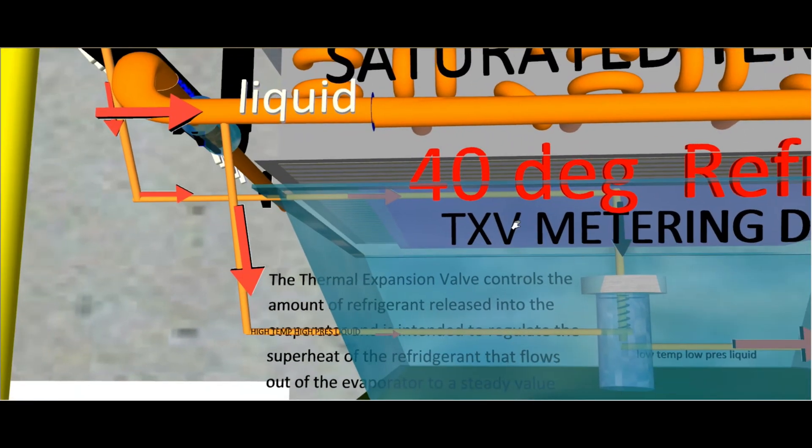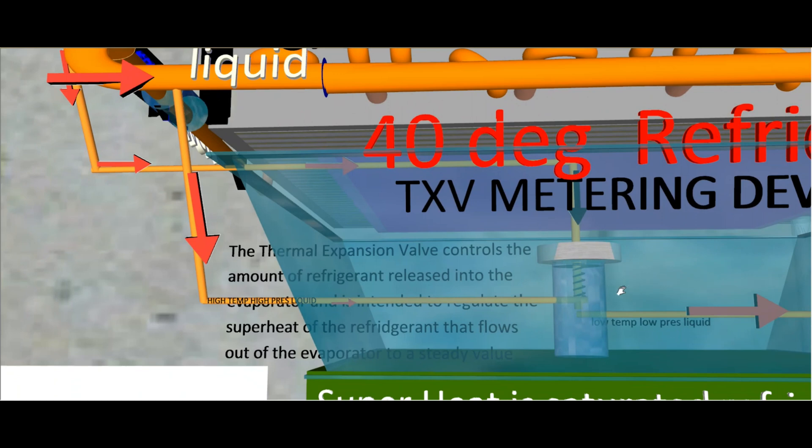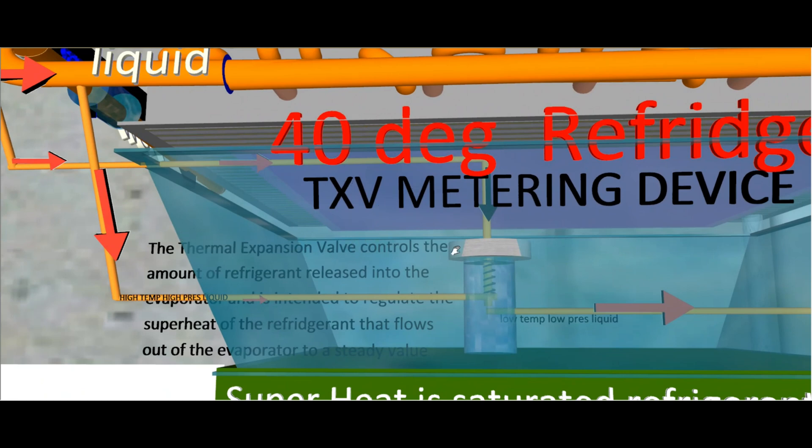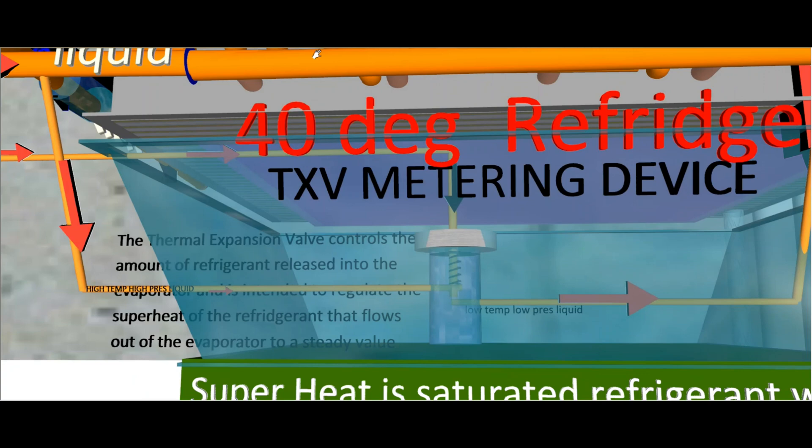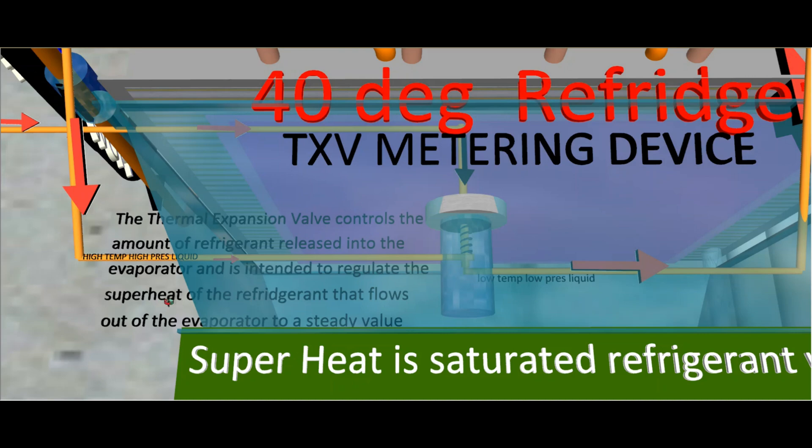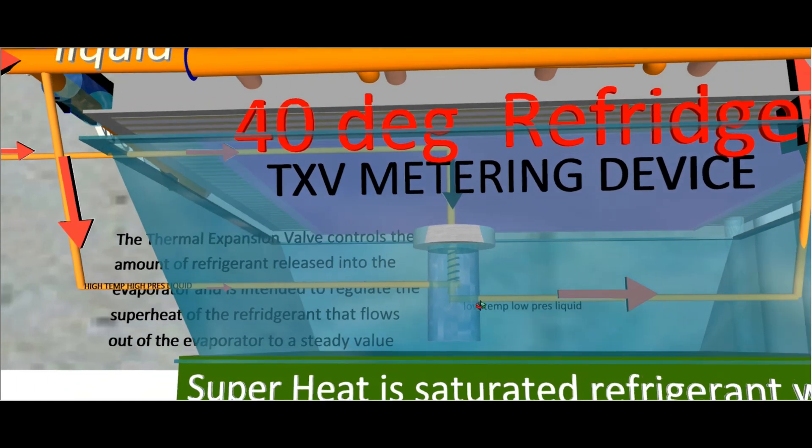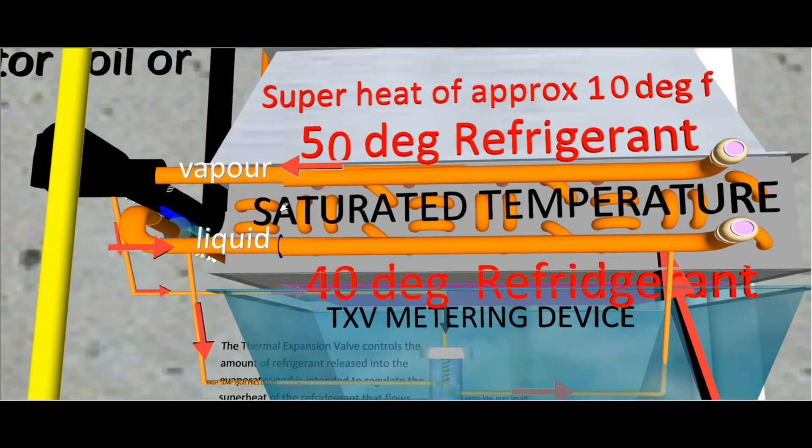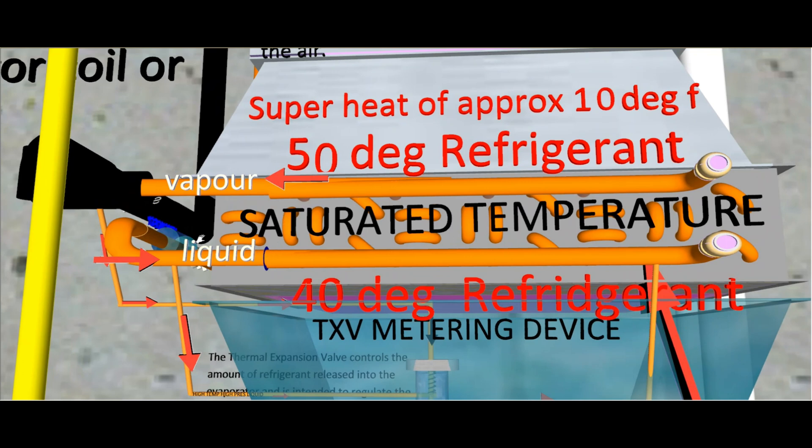And another name for this metering device—there's two or three different kinds—the one I'm using apparently is the popular one, the thermal expansion valve. It controls the amount of refrigerant that goes through the evaporator coil and is intended to regulate the superheat of the refrigerant that flows out of the evaporator to a steady value. So it's going to decrease it down this small tube, and that is going to give it a lower pressure. The lower the pressure, the lower the temperature.